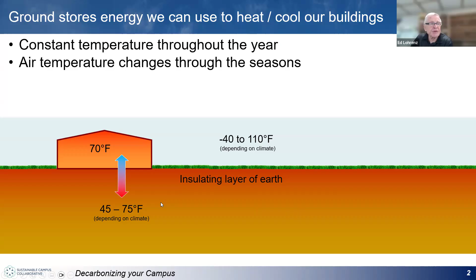So what we do with a ground source system is build a heat exchanger in the ground, and typically that's made of plastic pipe, similar to the pipe that the gas company uses, and circulate fluid through that. As the fluid circulates, it becomes about the same temperature as the earth around it. That fluid then circulates through a heat pump that's located in the building. The heat pump either cools that fluid and uses the heat taken from the fluid to heat the building or make hot water, or vice versa. It's taking heat from the building when you're cooling the building and rejects the heat to the ground.